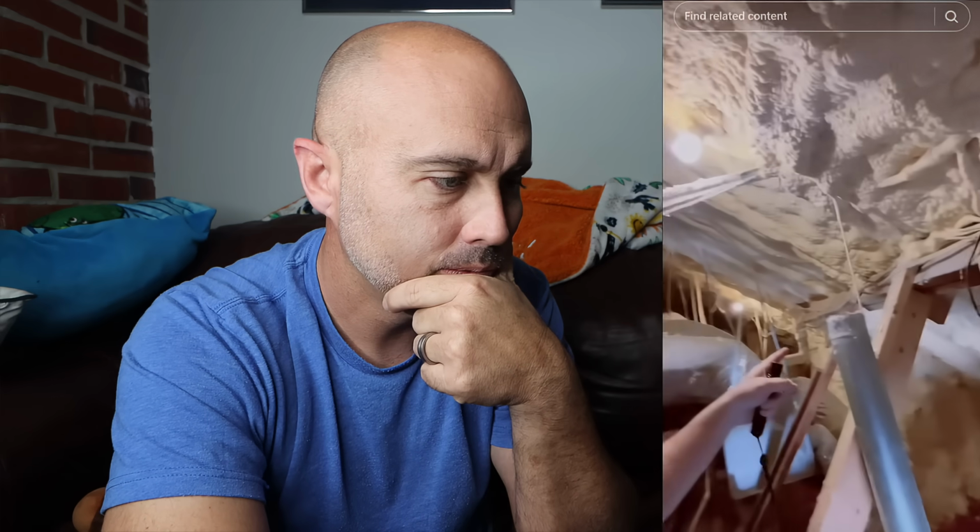For whatever reason, the audio was terrible, so I'm just going to do a voiceover. The other thing they messed up on is they basically capped the dryer termination. And so you saw that dryer termination, it's just pumping lint straight into the attic. And humidity.